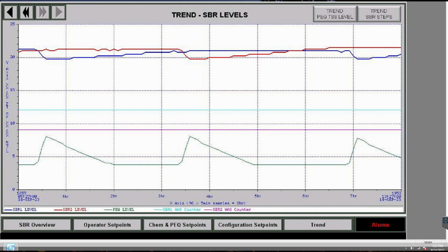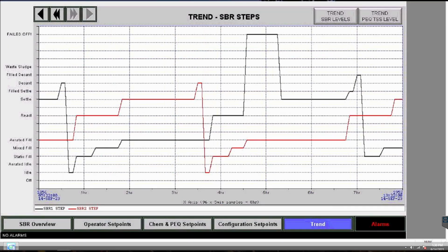So let me ask this: how many SBRs do you have in the system? Just 2. 2 means 2 tanks. One sequencing batch reactor, but 2 tanks, if that makes sense. It's not a single tank. Plus an influent equalization basin. That's right. Okay. Well, in a 2-tank system, because of the limitations we talked about earlier, one tank has to be in fill at any given time.